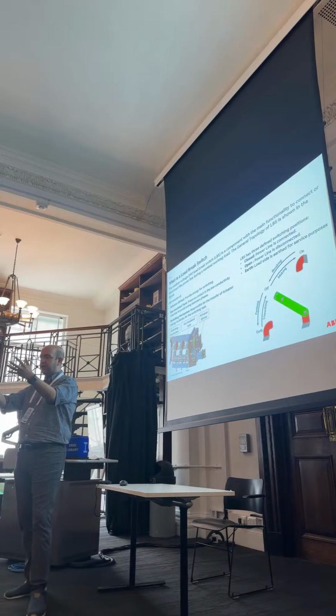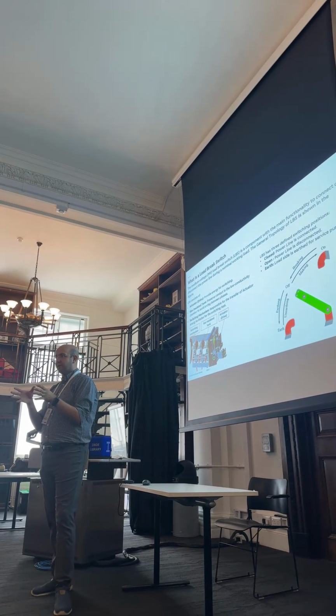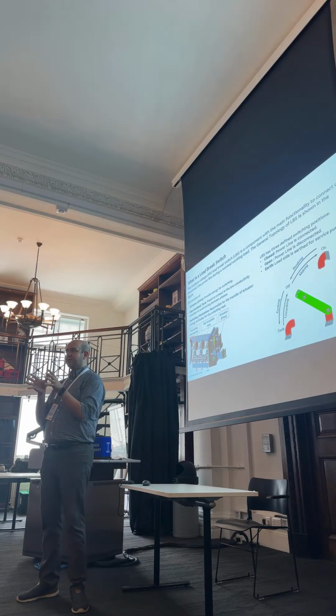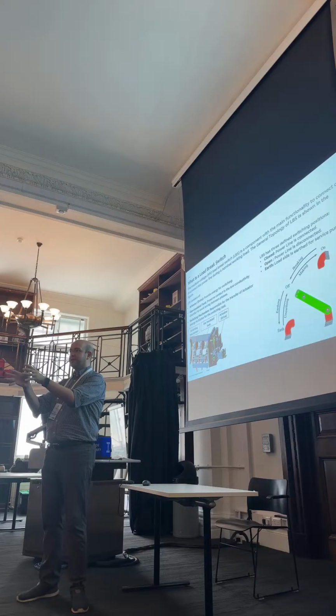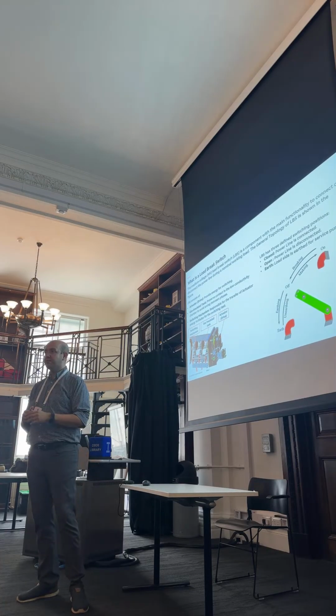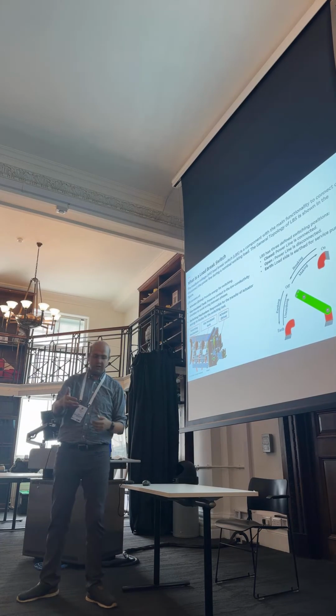Assume that you're in a city, the power connects to many home appliances, and in each of them there is a capacitor. And then the technician wants to do some modification on the device and touch the system in an off state. All the capacitors on the downstream of your system will electrocute the operator. That's why we need this earthing mode to make sure that we discharge any remaining electricity on the downstream of the line. So that's quite important.